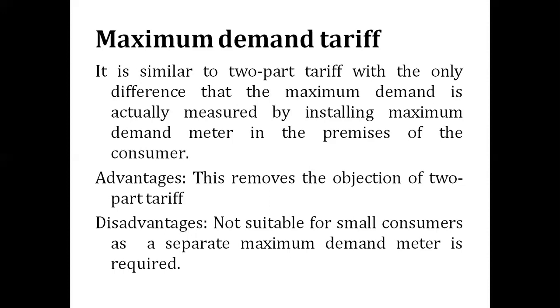With a Maximum Demand Meter installed in the consumer's premises, the actual maximum demand for each consumer is measured, so each consumer pays for their particular measured demand. This removes the objection of the Two-Part Tariff, where the measurement issue can be nullified.